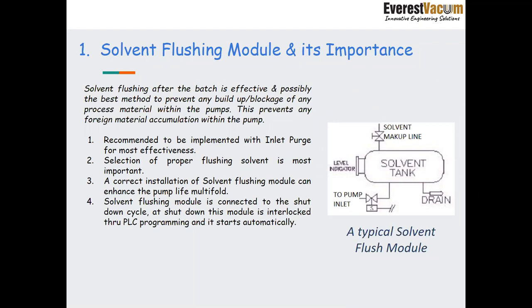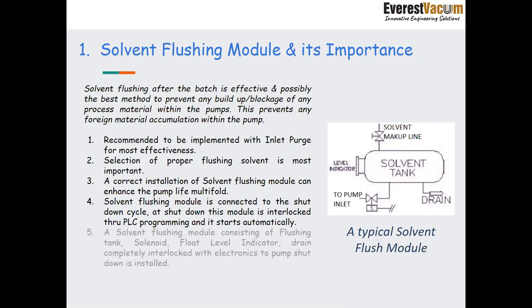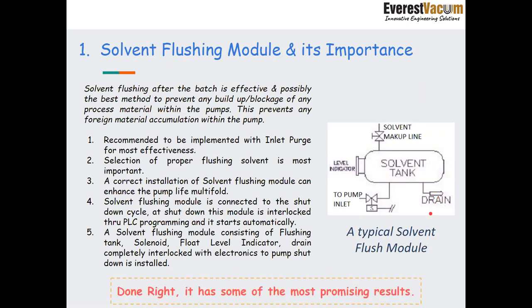And the solvent flushing module is connected to the shutdown cycle. At shutdown, this module is automatically interlocked via PLC programming, and it comes into play the moment you stop the pump. So a solvent flushing module consists of a flushing tank, then this solenoid, then there is an option available of a float level indicator, then a drain, and it is all pre-programmed to clean out the pump towards the end of the cycle. So done right, it has some of the most promising results.